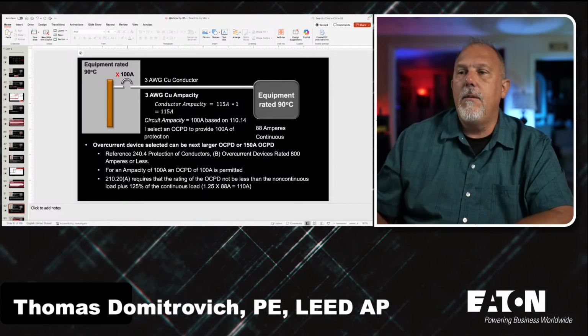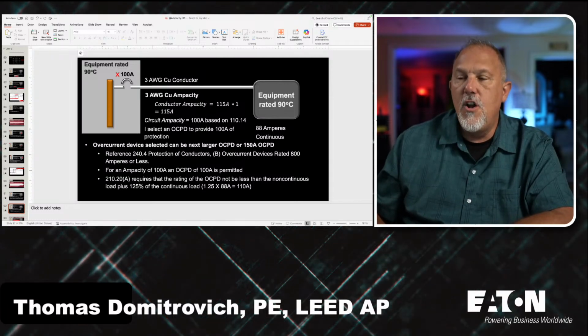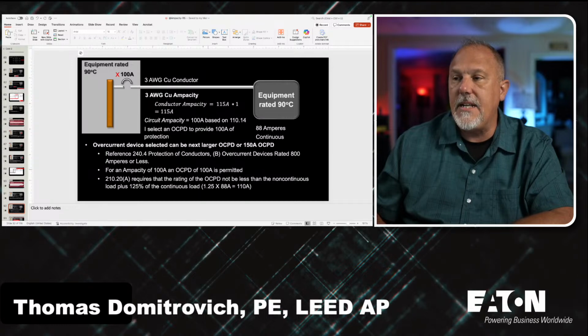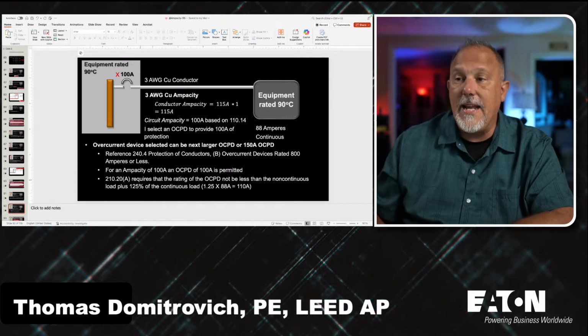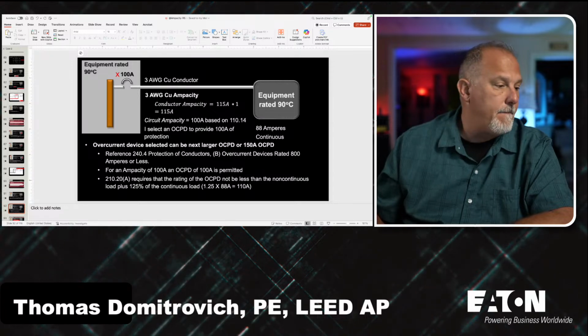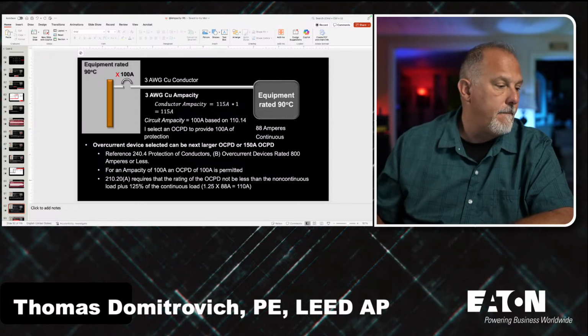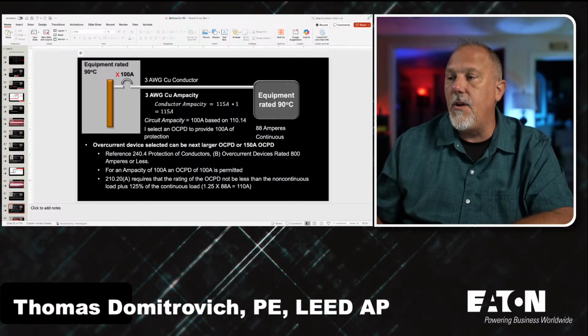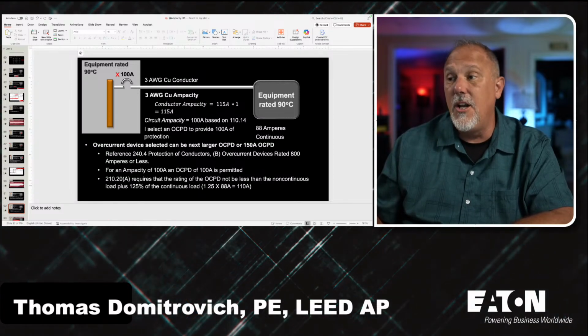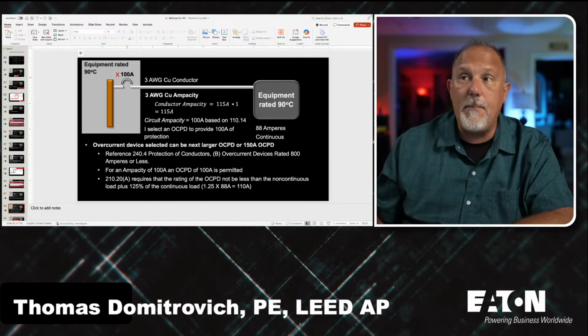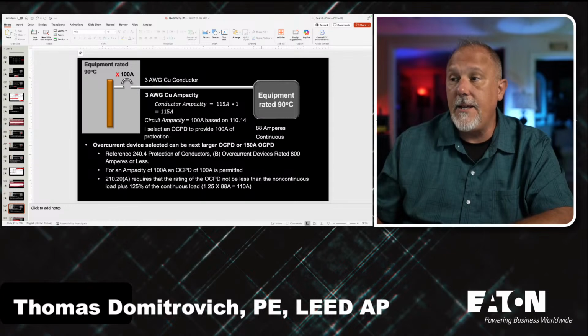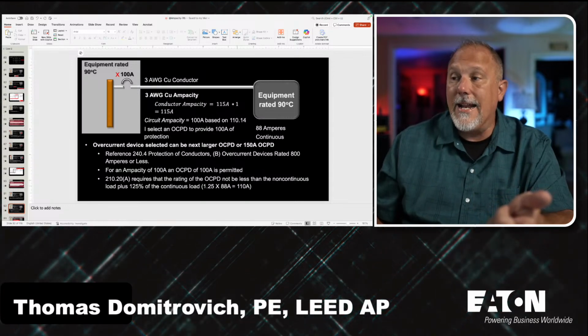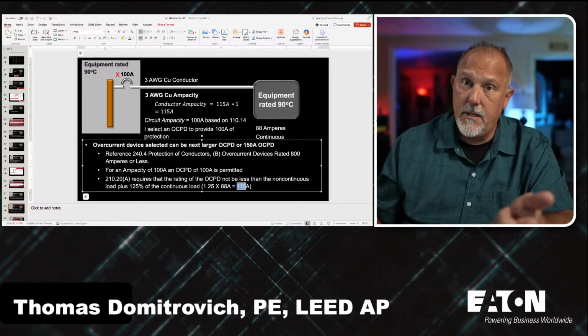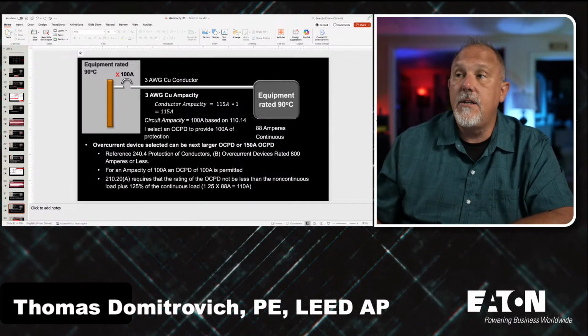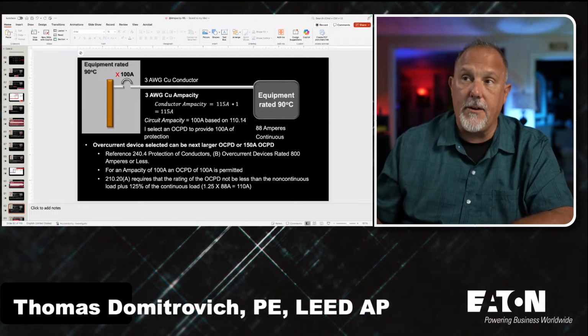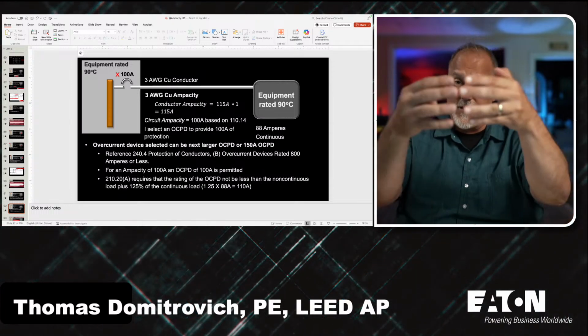But remember, based upon the ampacity of 100 amps, an OCPD of 100 amps is permitted, but 210.20(A) requires that the rating of the OCPD not be less than the non-continuous plus the continuous. So my OCPD cannot be 100 amps. It has to be at least 110 amps. So that means I can't do a 100 amp breaker. Not gonna work.